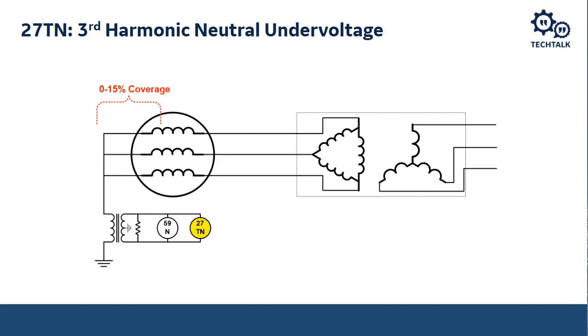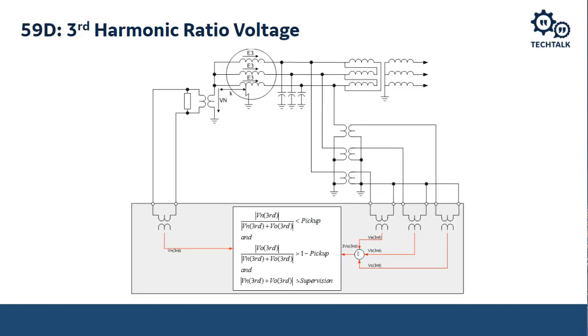As I mentioned, that gives us the additional 0 to 15% coverage that we might not get out of the 59N element. And the 59D element, the third harmonic differential or ratio voltage, as I mentioned, takes the measurement of the transformer neutral, compares it to the calculated voltage measurement from the terminals, and does a differential between the two to detect that there's an issue within the generator, a ground fault within the generator.